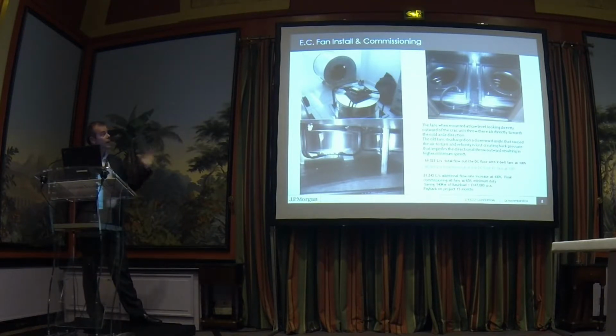So basically we had all the air conditioners running. I went around and along the entire floor, measured all the airflow. We had 69 cubic metres a second of air out of all the machines, out of the data center floor. That was all the fans at 100%, the V-belt drive ones. We put the new EC in, now we're getting 93 cubic metres a second at 100%.